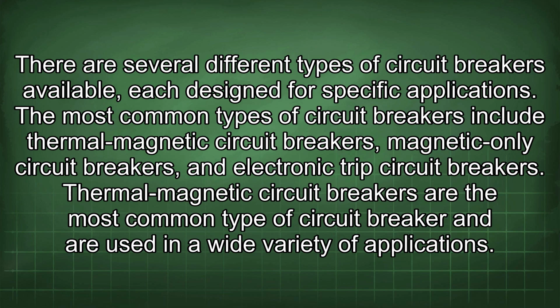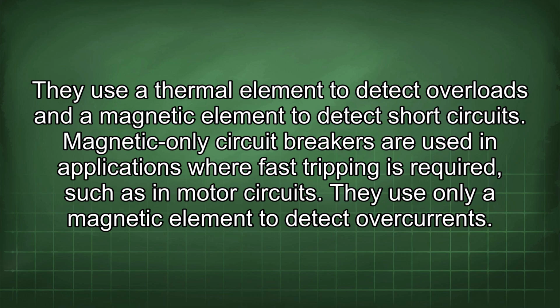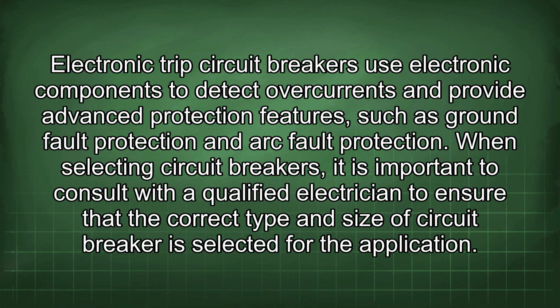Thermal magnetic circuit breakers are the most common type of circuit breaker and are used in a wide variety of applications. They use a thermal element to detect overloads and a magnetic element to detect short circuits. Magnetic-only circuit breakers are used in applications where fast tripping is required, such as in motor circuits. They use only a magnetic element to detect overcurrents. Electronic trip circuit breakers use electronic components to detect overcurrents and provide advanced protection features, such as ground fault protection and arc fault protection.